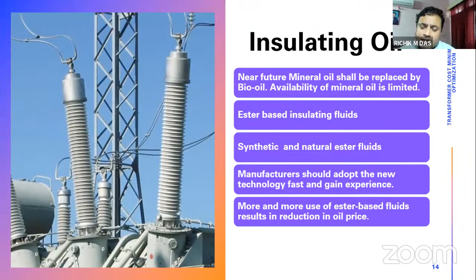In the global scenario, many manufacturers and utilities are doing a lot of research on this topic, and Power Grid is also doing so. We have successfully commissioned one 400 kV reactor with natural ester, and we are planning one 400 kV transformer with synthetic ester. We are also doing some retrofilling of transformers and reactors with ester-based fluid. This is the next generation's requirement, and many manufacturers should come with this solution. Definitely the cost of the oil will be reduced if the demand increases day by day. So this is also a major challenge for us.